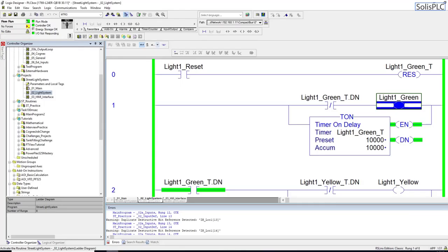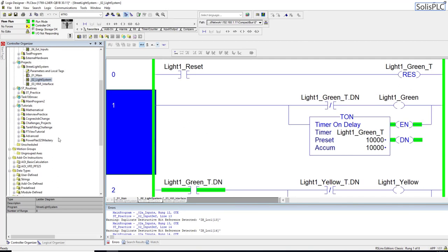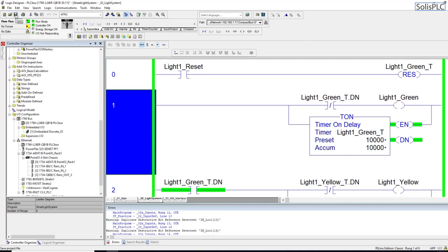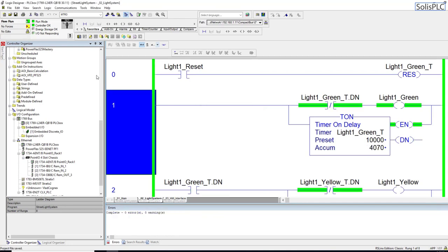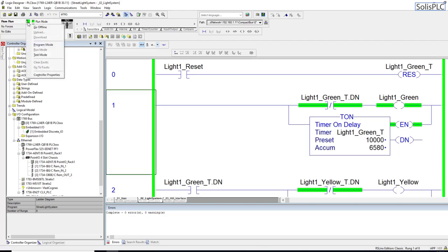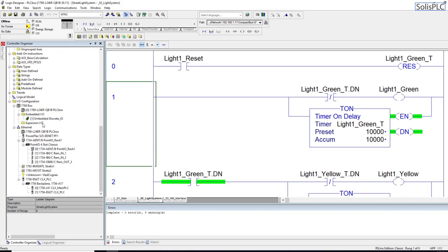That being said, let's go back into the PLC. And before we start adding modules, we do need to save the program. So I'm going to hit save. I'm going to hit yes, just like I do every single time that I go offline in order to make some changes. I'm going to then click on this remote run, and I'm going to disconnect from my controller by saying go offline. And here in the embedded discrete IO on my processor, remember that it's a 1769-L24ER-QB1B PLC. So it's a CompactLogix, which is able to accept modules to the right side of it.